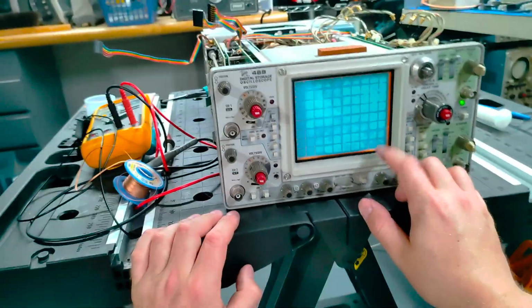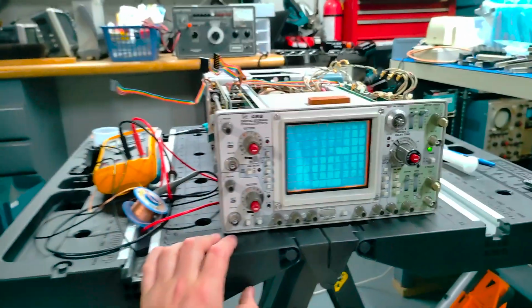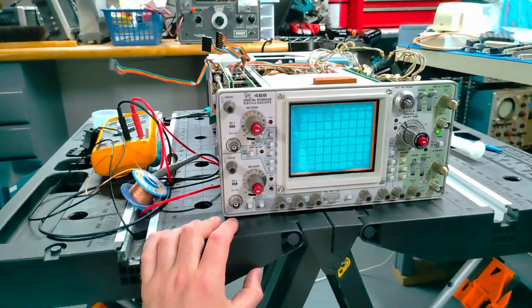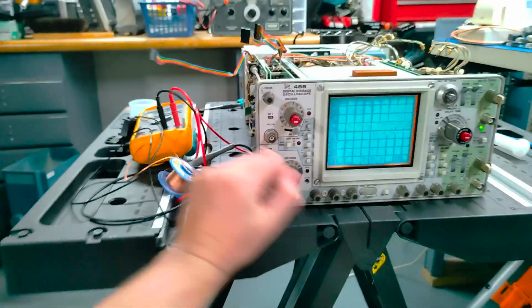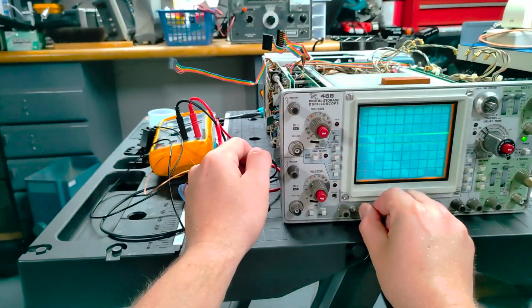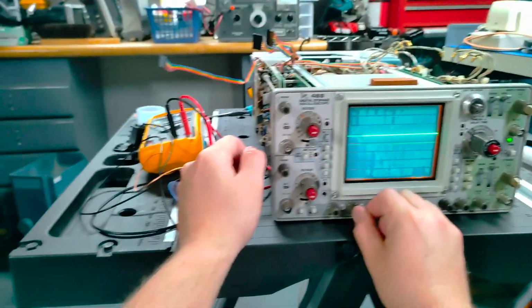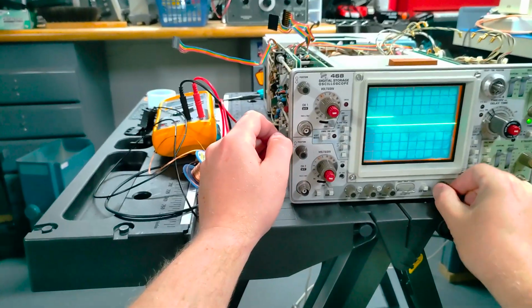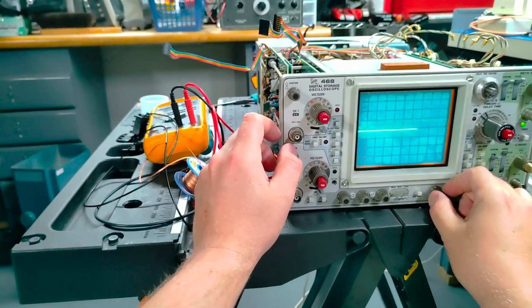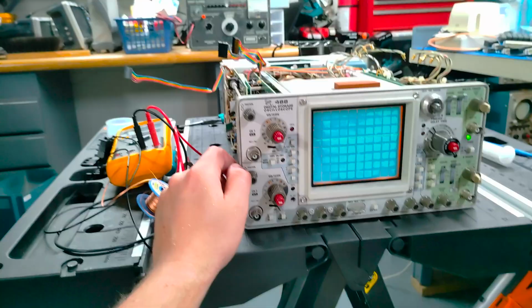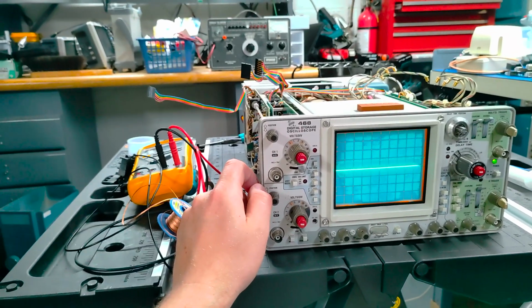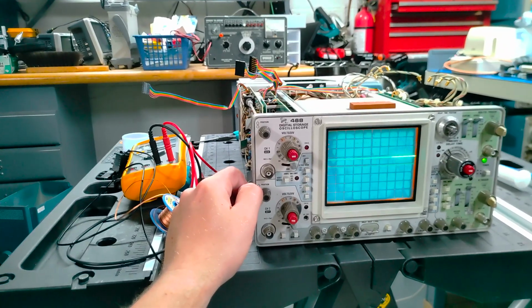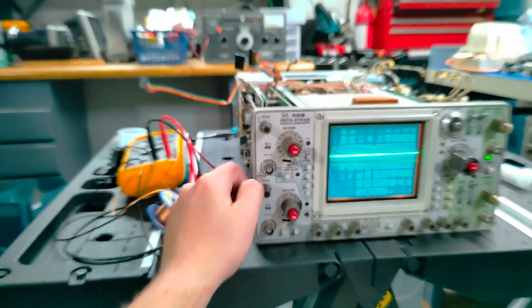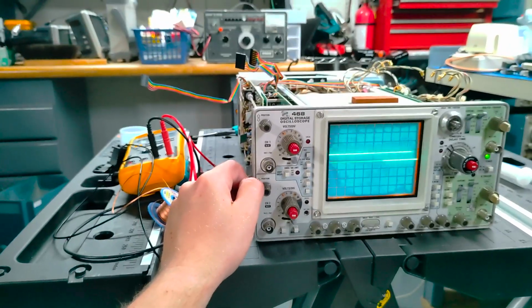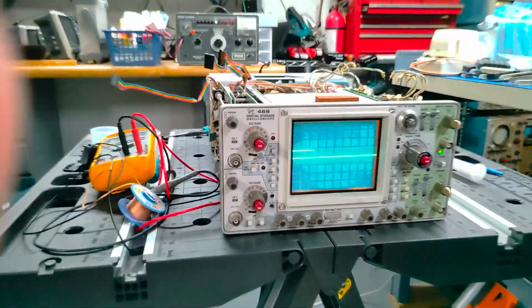Well, the scale illumination lit up. That's a good sign because that wasn't lighting up when the power supply was dragged down. So look at that. Let's get the focus. Move left and right. We got two traces. I would say that's fixed. So yeah, that cap was bad. It had bad insulation resistance, so it was leaking all the current to ground. All right, let's get the top back on and close this thing up.